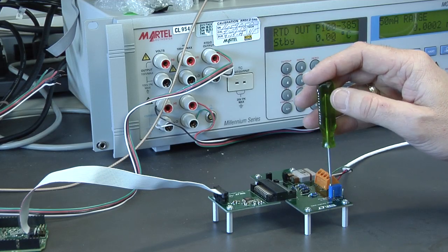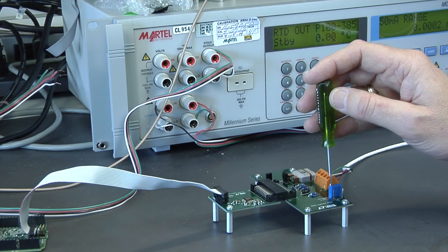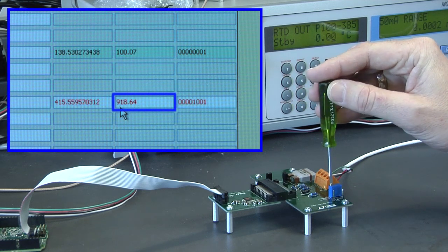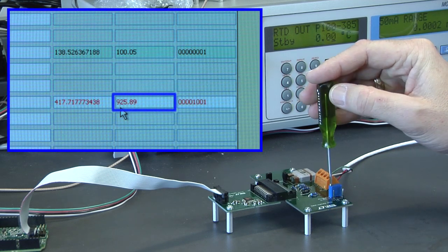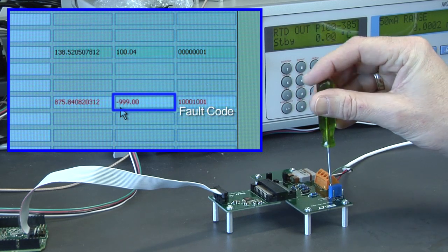The LTC2983 contains many fault reporting mechanisms. By adjusting the variable resistor RTD simulator, it is possible to create soft faults, sensor temperature above or below the RTD range, and hard faults, RTD short or open, R-sense short or open.